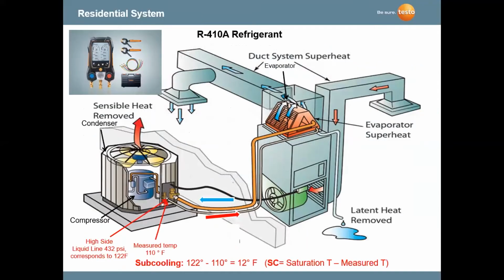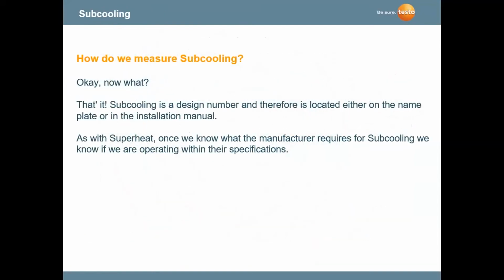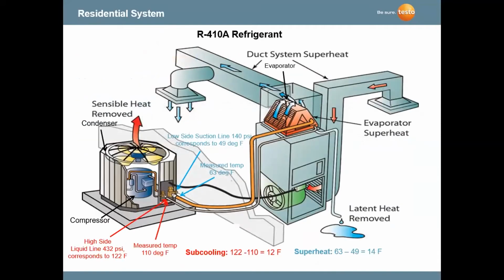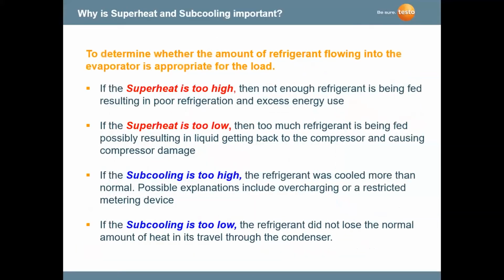And again, subcooling is the saturated temperature minus the measured temperature. And subcooling is a design number from the manufacturer. That's usually on the nameplate or in the instruction manual. So you've got two sides that you're looking at: the low side and the high side, subcooling on the high side and superheat on the low side. And here are some interesting things about superheat and subcooling. Most of you, I'm sure, know this already, but it's a repeat of what we talked about.